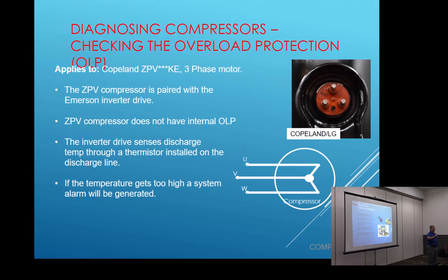Our variable speed scroll compressor is a 3-phase compressor. So if we're ohming that compressor out and we're going across each leg, what common characteristics should each leg have? They're all supposed to be the same. All supposed to be the same, right. So we might have 1 ohm on every one of them, or 2.5 ohms. But if we have 2.5 ohms, 2.5 ohms, and 5 ohms, oops, Houston, we have a problem, right?